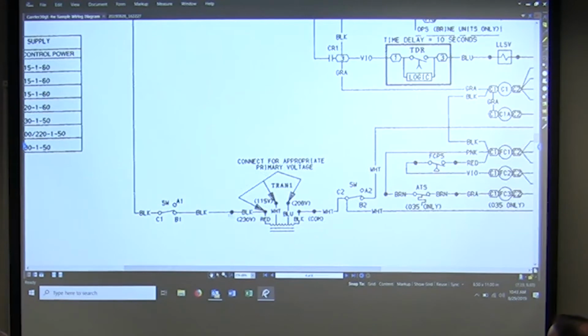What about this guy right here? Transformer connect depending on voltage. Okay, so we have a transformer. Anytime you see these squiggle lines with the solid bar or double bars, that's indicating I'm using a transformer. It's a symbol for transformer. We have a 230 volt tap, a 115 tap, a 208 volt tap. So depending on the type of system I'm hooking up, I'm going to use one of those voltages, okay?